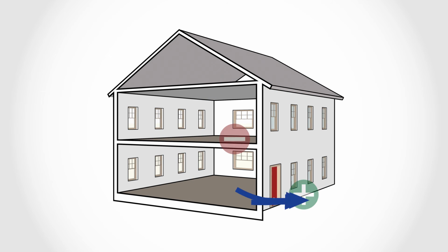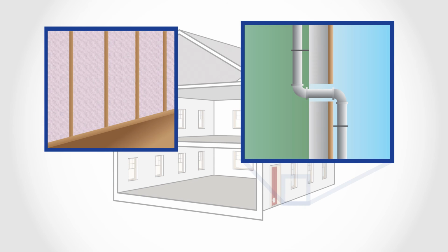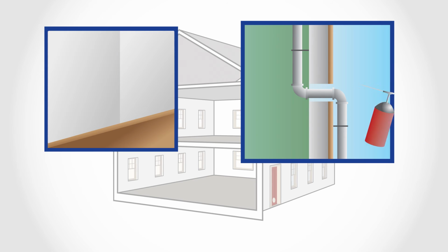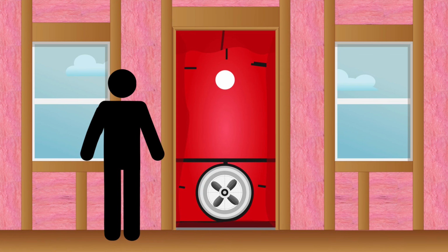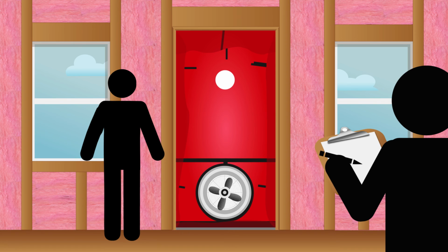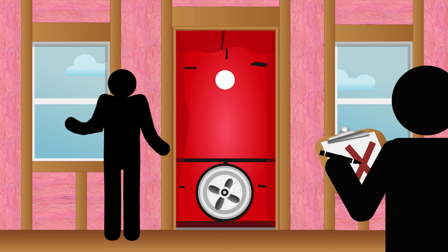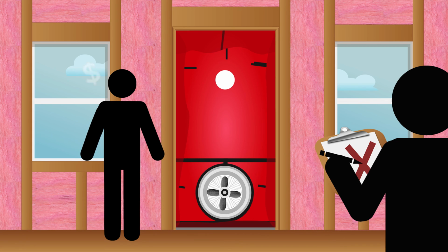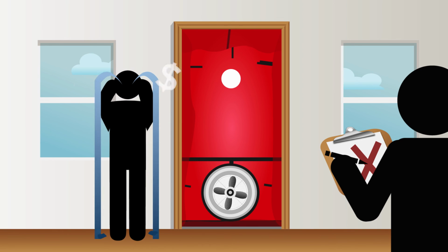The blower door test used to comply with the law must be performed when the structure is complete, including all drywall installed and all penetrations properly sealed. All HVAC systems must also be installed, and all subcontractors should have completed their work so no further inadvertent penetrations are made. It is good practice to perform preliminary blower door tests during construction to make sure the project is on track to pass the final blower door test and to avoid costly delays. It is cheaper and easier to repair air leaks before the drywall is completed.